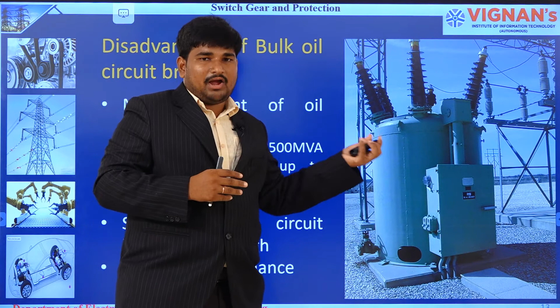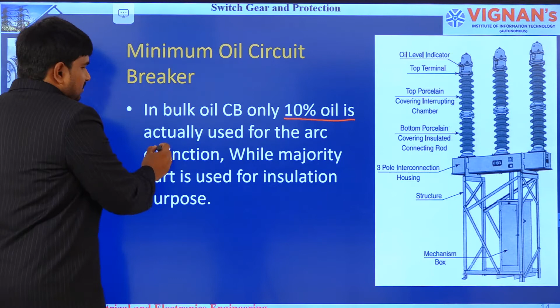So what is a minimum oil circuit breaker? In case of bulk oil circuit breaker, the oil is used for two purposes. One is for insulation purpose and the second is for arc quenching. Of the total amount, only 10% is used for arc quenching, and the remaining oil is used for insulation purpose only. In bulk oil circuit breaker, only 10% of the oil is used for arc extinction. The majority is used for insulation purpose only. So that is the disadvantage of bulk oil circuit breaker.